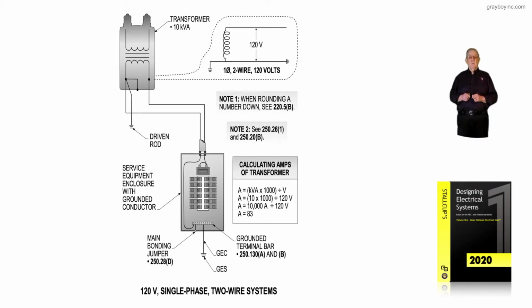This illustration deals with a 120 volt single phase 2-wire system. Notice in the illustration the transformer rating is 10 kVA, but we're only taking 120 volts from the transformer. So we have a 120 volt single phase 2-wire system supplying the panel board. What this illustration illustrates is what would be the amp rating of the ungrounded conductor terminating in the breaker, as you see in the illustration.